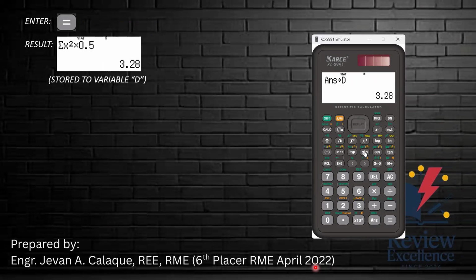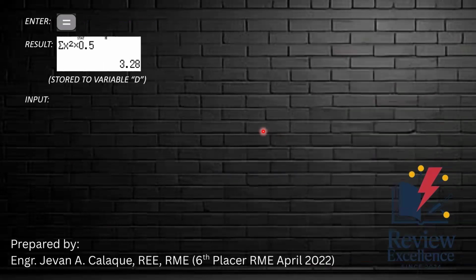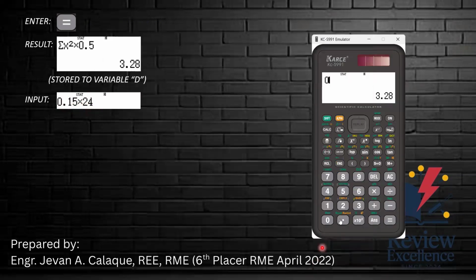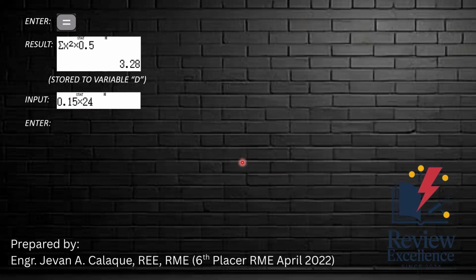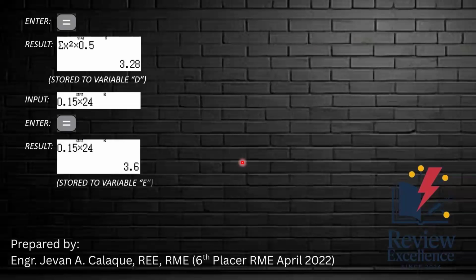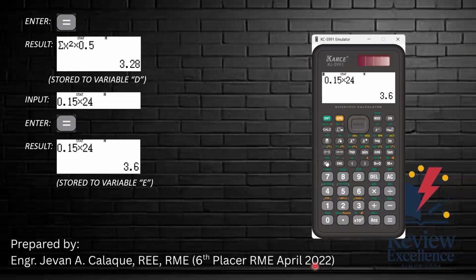And then next, we input our core loss, which is 150 watts. In terms of kilowatts, that is 0.15. For the core loss, engineers, we multiply by the whole day, which is 24 hours. So 0.15 times 24, equals. The result here is 3.6, stored to variable E. Okay?